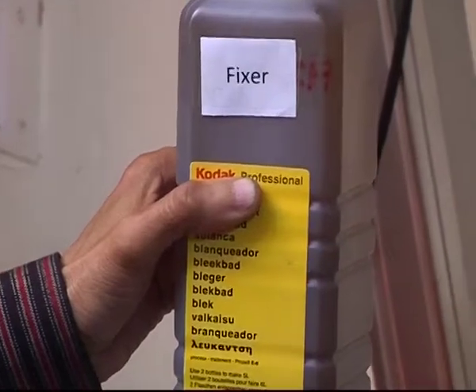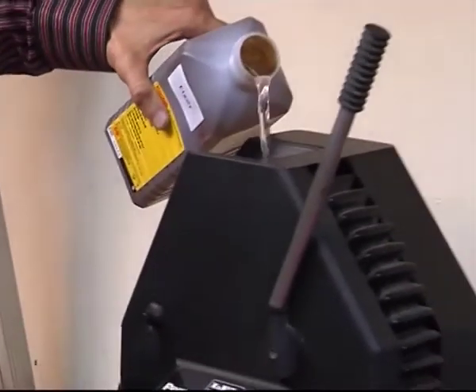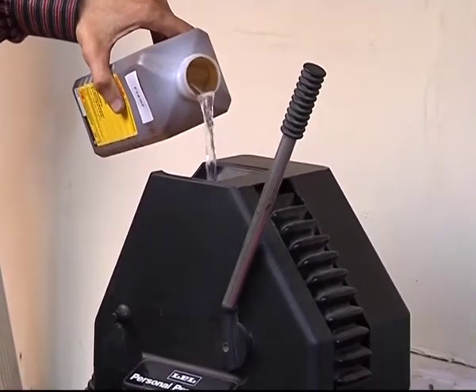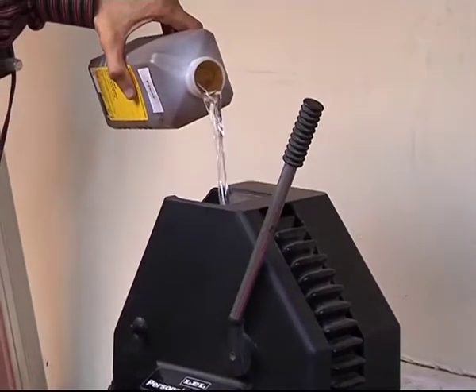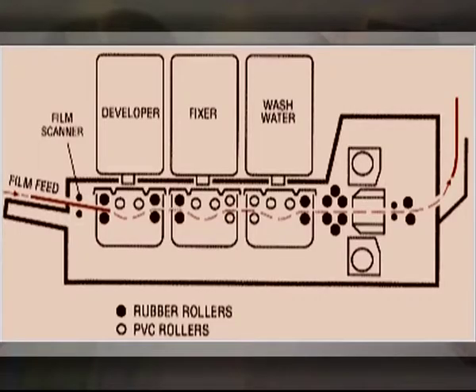Fixing. After leaving the developer, the film is transported into a second tank, which contains the fixer solution. The fixer is a mixture of several chemicals that performs the following functions. Neutralizer. When a film is removed from the developer solution, the development continues because of the solution soaked up by the emulsion. It is necessary to stop this action to prevent overdevelopment and fogging of the film. Acetic acid is in the fixer solution for this purpose.